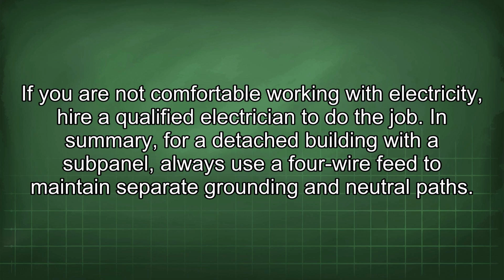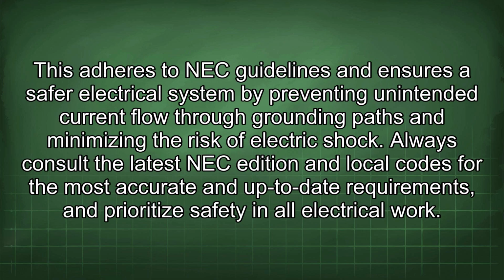In summary, for a detached building with a subpanel, always use a 4-wire feed to maintain separate grounding and neutral paths. This adheres to NEC guidelines and ensures a safer electrical system by preventing unintended current flow through grounding paths and minimizing the risk of electric shock. Always consult the latest NEC edition and local codes for the most accurate and up-to-date requirements, and prioritize safety in all electrical work.